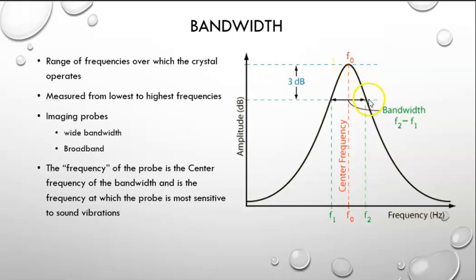Well, the high end is going to be where the probe is less sensitive by an amount of 3 decibels, or if you remember how decibels work, it's half as sensitive to this frequency at f2 as it was to the frequency at f0. So we have a 3 decibel loss, and we're going to say that's where our high-end frequency is. When we lose our sensitivity to 3 decibels for the low end, we're going to say that's our low end.